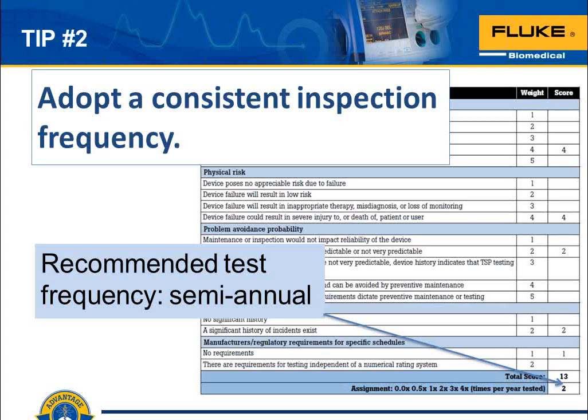So the service manual inspection procedure from the manufacturer is the number one top choice. But if that's not available, the frequency of inspection must still be determined. You don't get away from it. You have to determine one. One method for doing that is to use a risk-based method, and there's one used by the University of Vermont Biomedical Engineering Department. We teach this in our medical device quality assurance curriculum in Advantage Training. And basically the way it works is this.